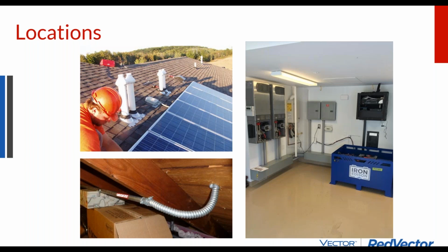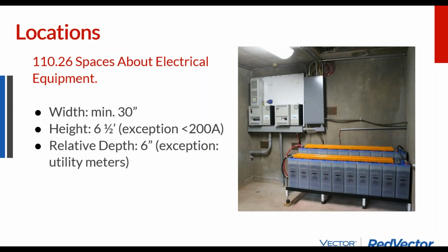So you have to be looking at your components to say, is this a wet rated component or just a dry component? Is this component rated for higher temperature or lower temperature? Is this rated for inside of conduit, or can it be rated for outside of conduit? All of that is driven by your location.